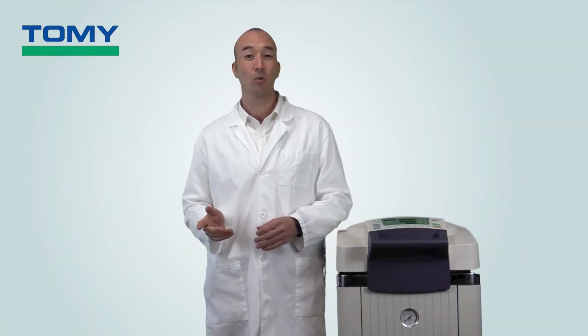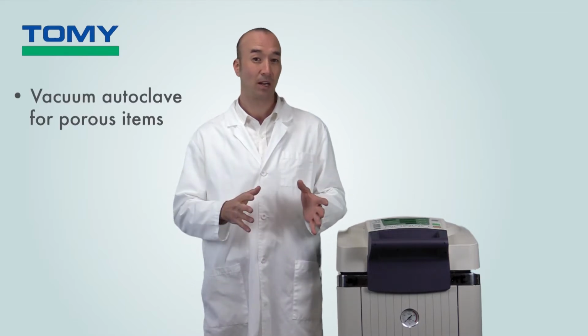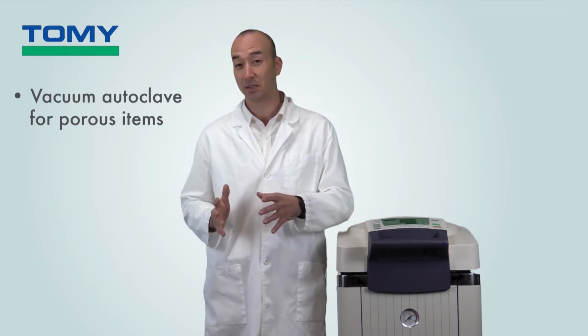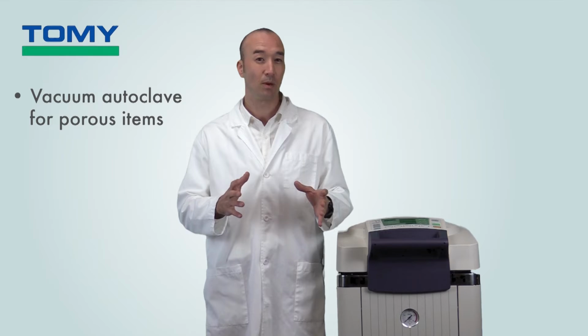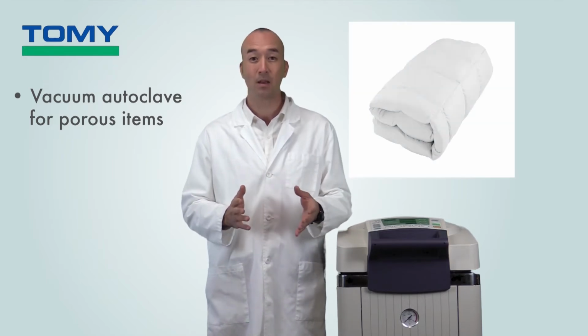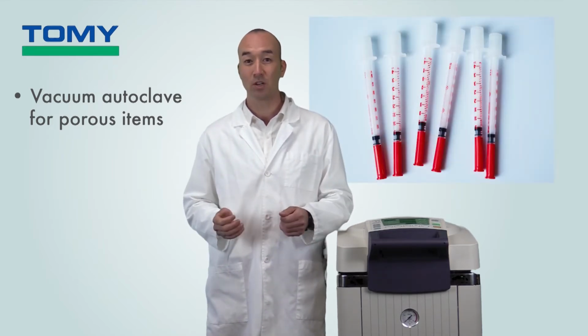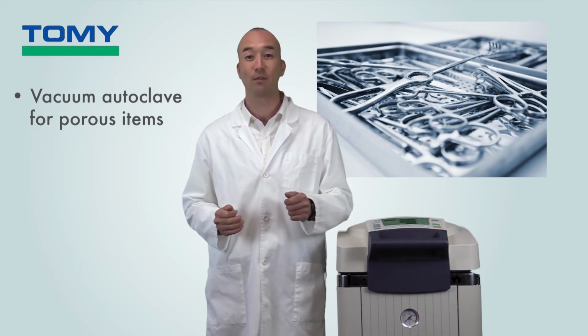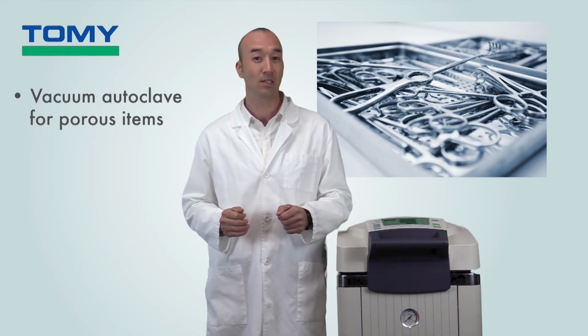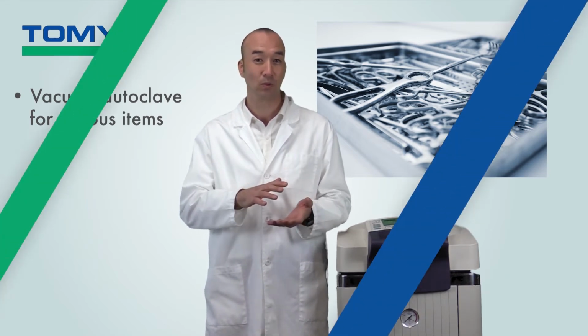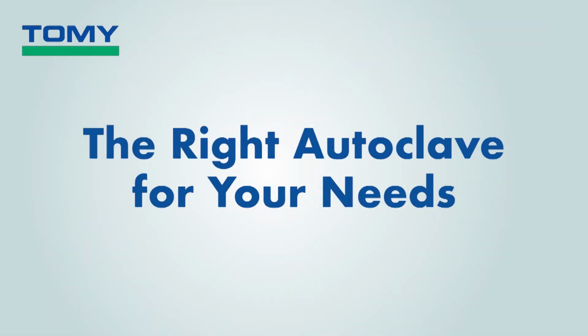As mentioned, you'll want to use a vacuum autoclave with porous items or items that have hard to reach spaces. This includes, but is not limited to, fabrics and bedding, polyethylene products such as syringes, or wrapped dry items that have air trapped inside, such as sterilization pouches that contain surgical tools. As mentioned earlier, your choice of an autoclave system will depend on the items that you'll be sterilizing.